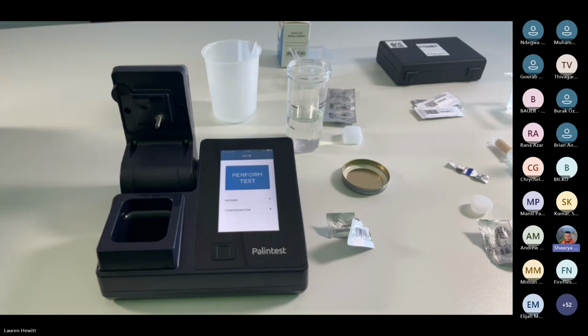So these sensors, when Lauren scanned in the QR code, it picks up the calibration. These calibrations have been done against lots of ICP-MS standard solutions. So we prepare at different levels, 5, 10, 50 ppb, and then we collect the data from that, and that is all encoded in the QR code. So when we scan the sensor, it picks up that data from the batch.